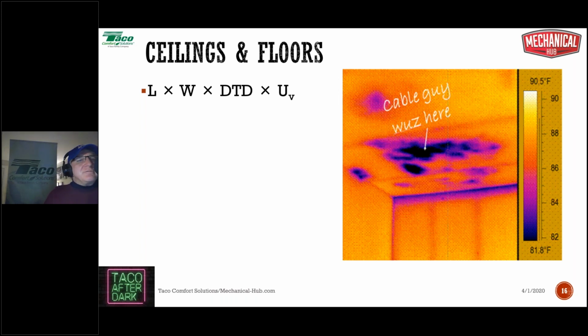There are certain circumstances when you'll do a ceiling loss and certain circumstances when you'll do a floor loss. They're not part of every room equation. A ceiling loss only applies if there's no heated space above. So if you've got a first floor with a heated second floor above, skip this step - there's no heat loss through the ceiling.